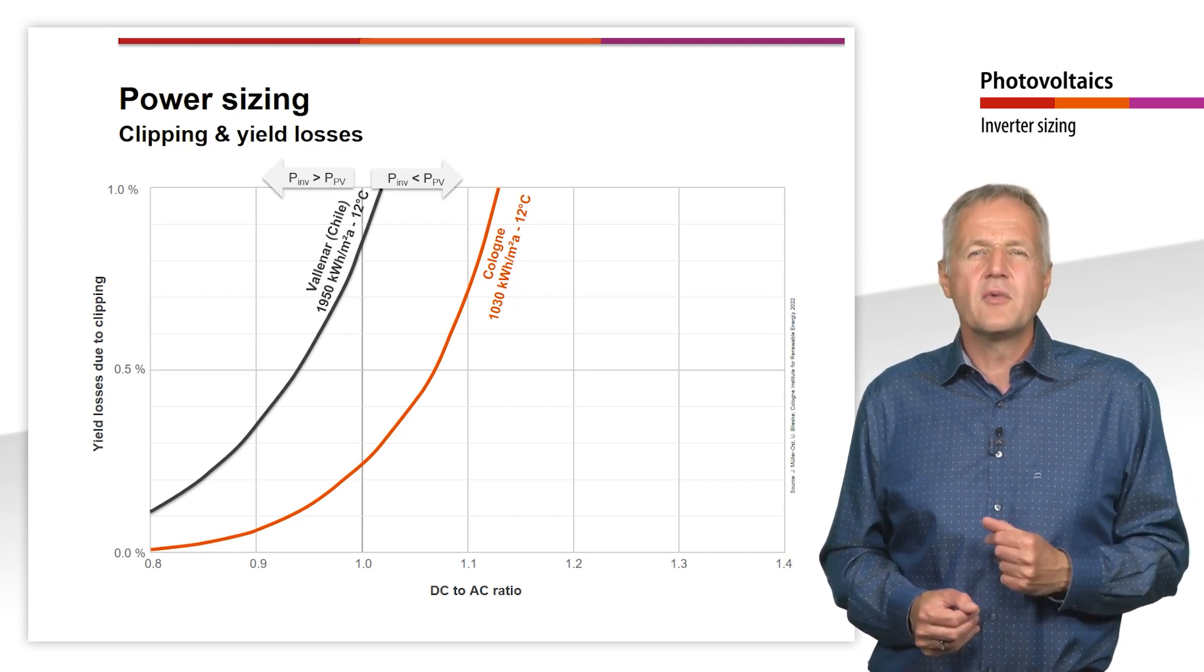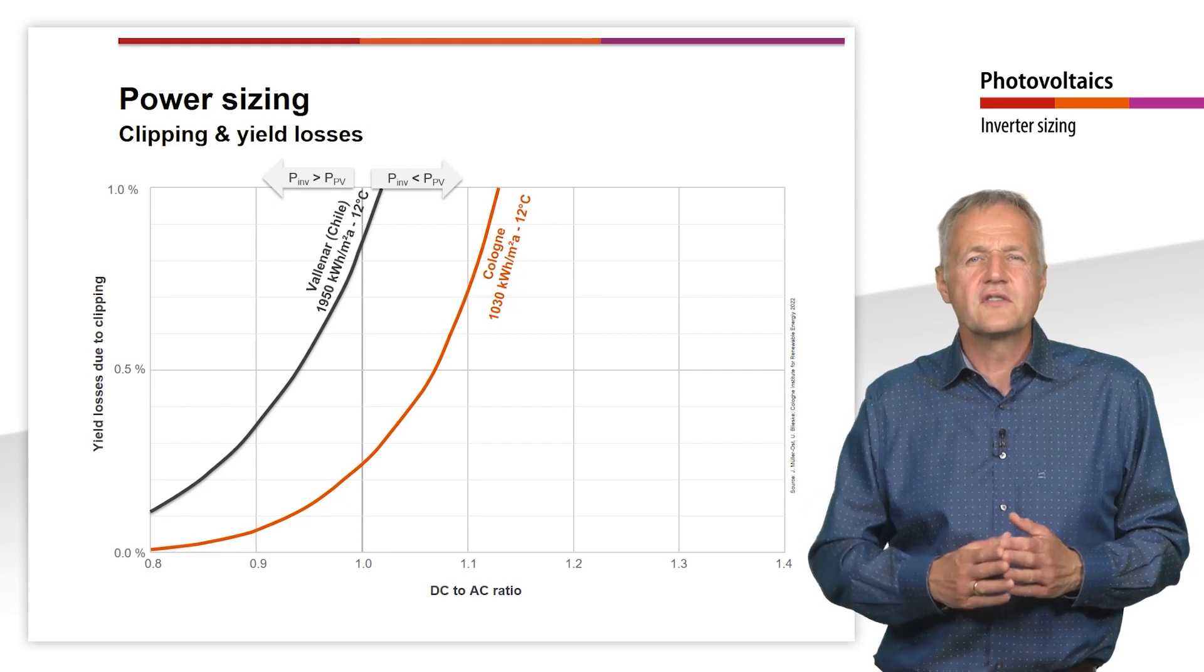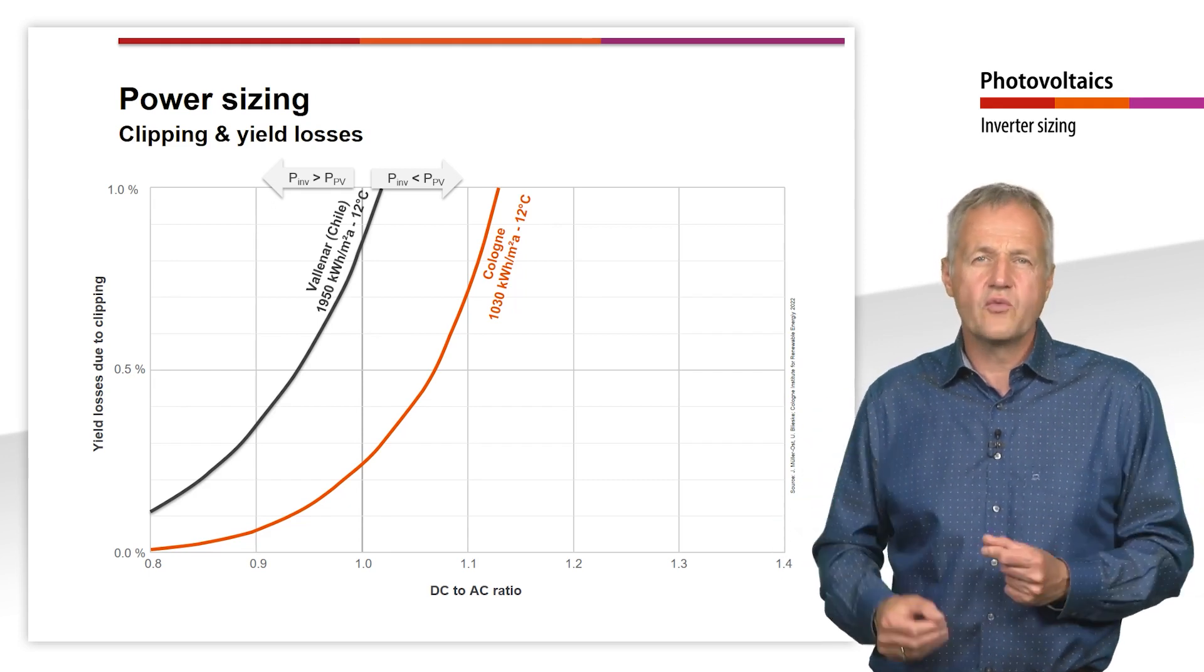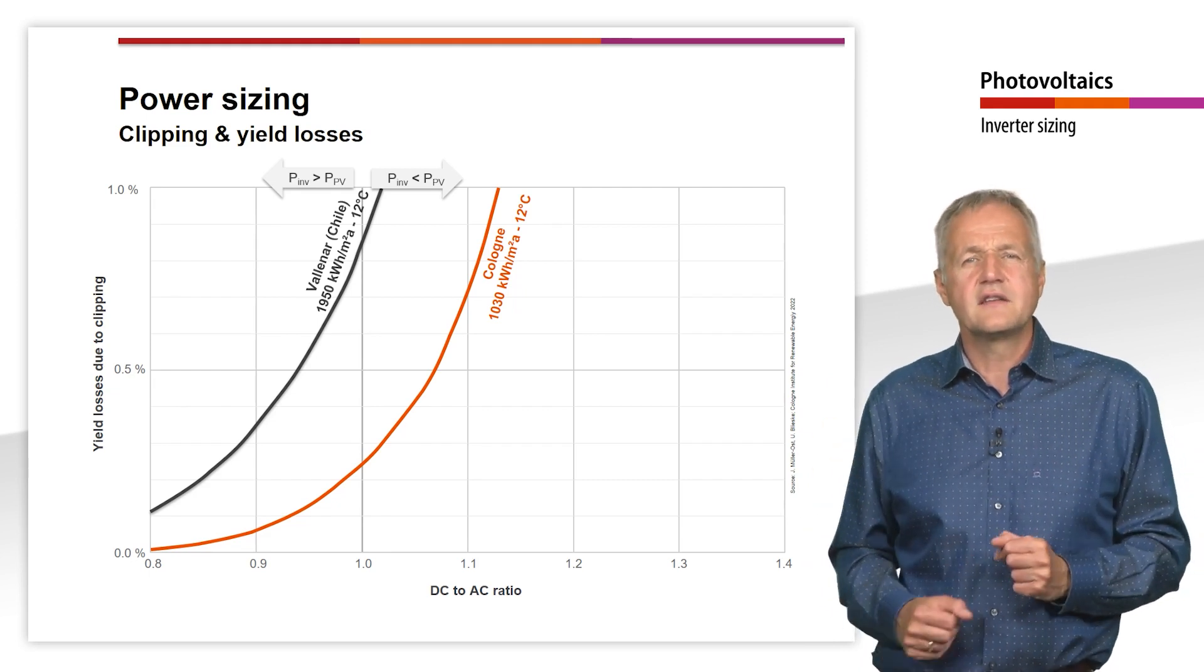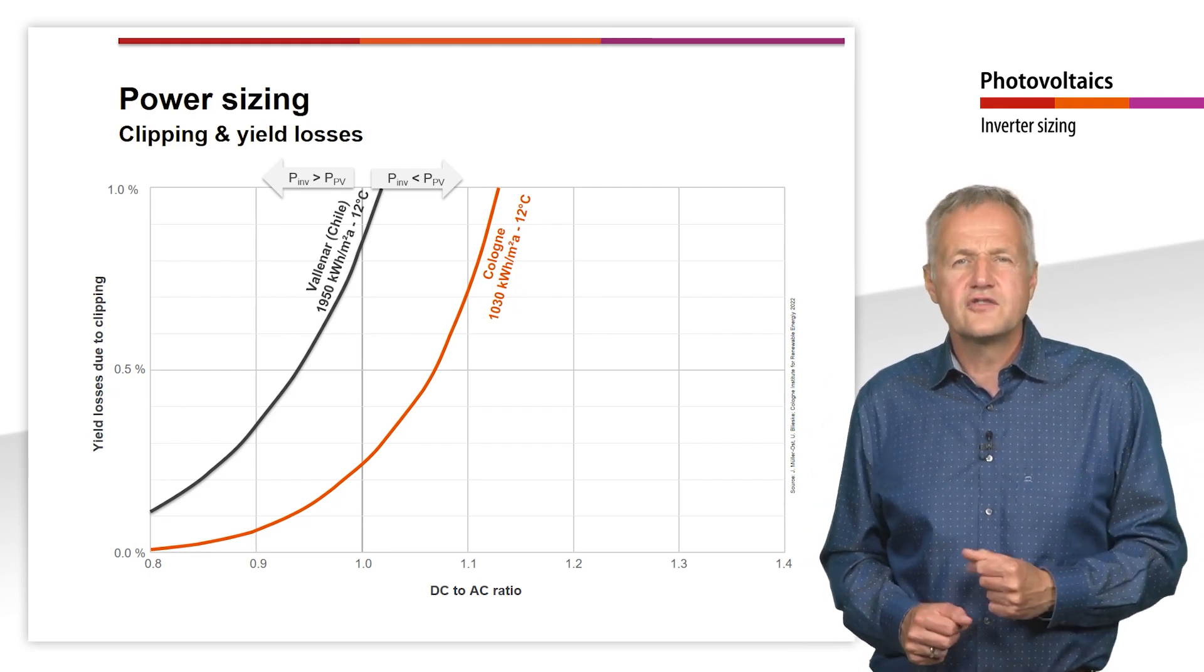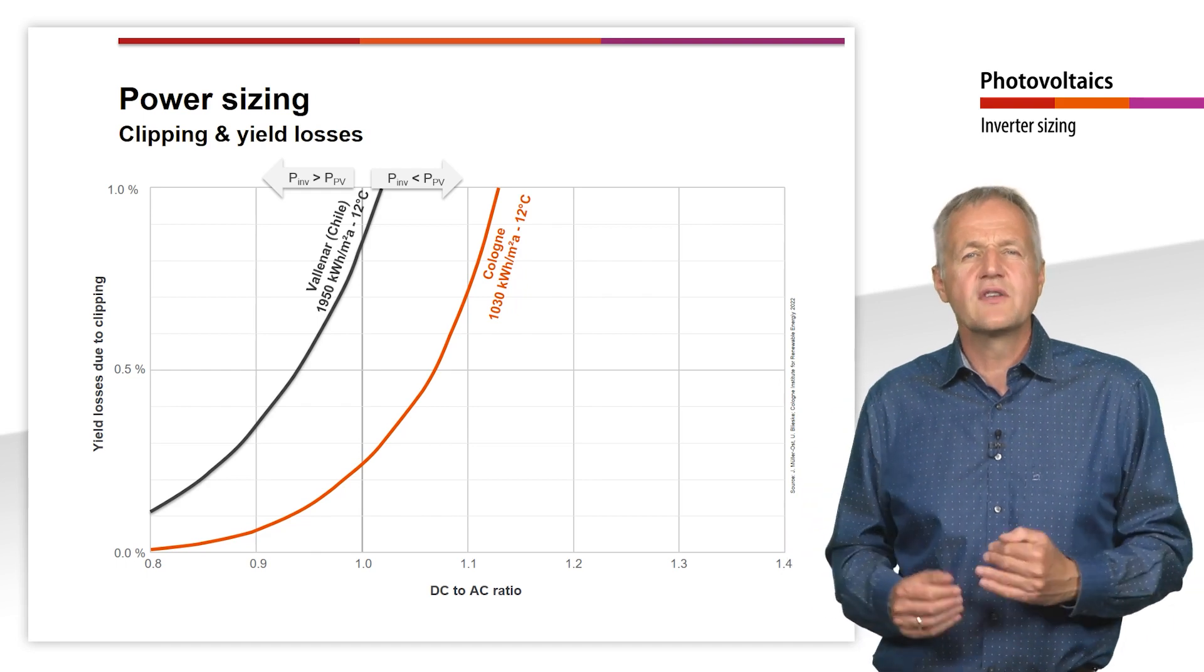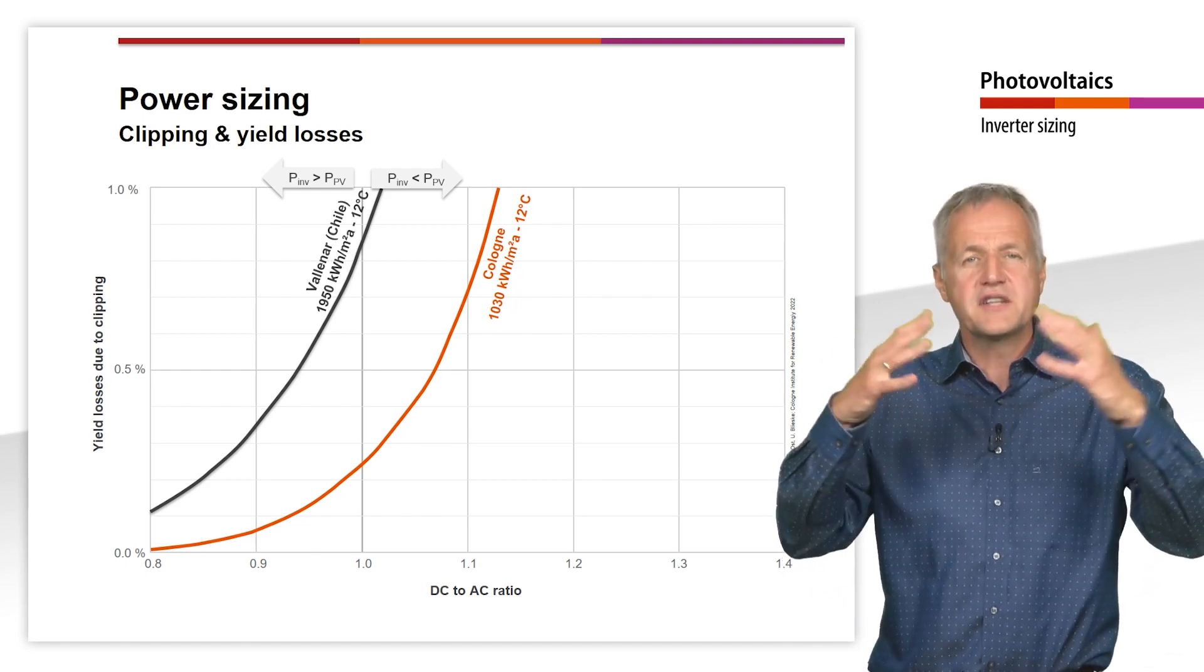With an optimal inclination of the modules, the design factor here should not exceed 1, so the inverter should not be undersized in any case. The situation is different for locations with high irradiation but also high temperatures.